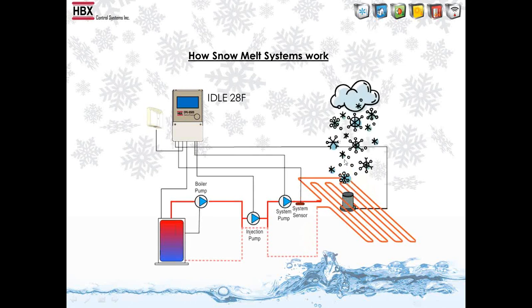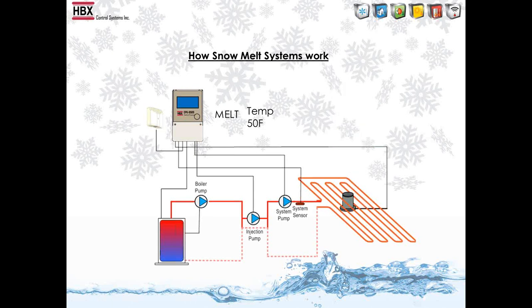Then if we get a little bit of snow on top of the snow melt sensor, we come out of idle and we go into melt mode, which takes us to a new melt temperature. What this does is it raises the set point of this slab from 28 degrees to 50 degrees. So now it comes out of idle mode and into melt mode. The snow goes away, we go out of melt mode, and we go back to idle mode. There is a time frame in there that you can set, and we'll talk about that as well, so that when the snow does go away, there is a melt time that will run after it stops seeing the snowfall. So once again, if you guys have any questions or concerns during this presentation, just don't hesitate to throw out a question.